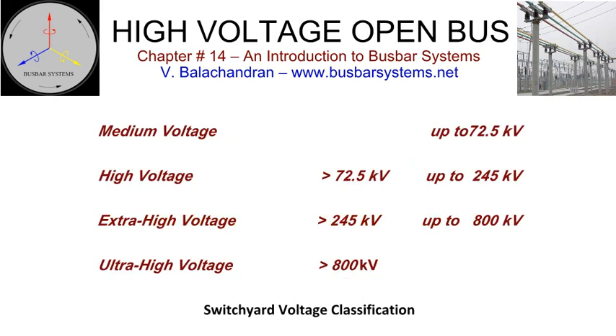ANSI/IEEE and IEC have different preferred rated voltages for medium voltage, high voltage, extra high voltage, and ultra high voltage systems. Minimum phase clearances, sectional clearances, and ground clearances vary with the rated voltages, are well defined in standards, and, in some cases, are project-specific. The voltage rating for a switchyard is classified as follows. Medium voltage, up to 72.5 kV. High voltage, greater than 72.5 kV and up to 245 kV. Extra high voltage, greater than 245 kV and up to 800 kV. Ultra high voltage, greater than 800 kV.